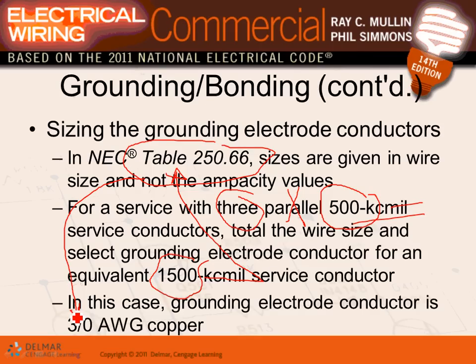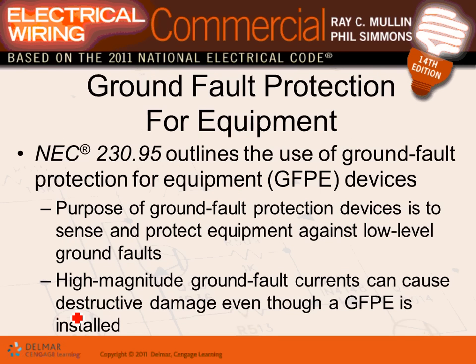Very simple, guys. For a grounding electrode conductor, you take the conductors that you sized with me for the service conductors and go to 250.66 to find the size you need. If you paralleled like we did, then all you have to do is multiply the size of one set by how many sets you paralleled, and go to the same table.